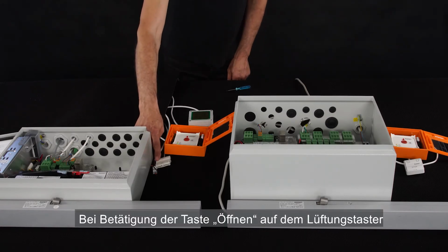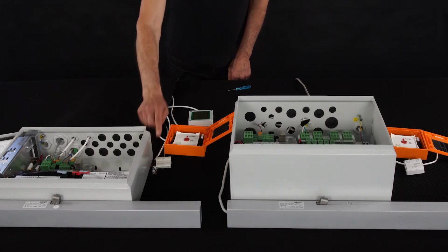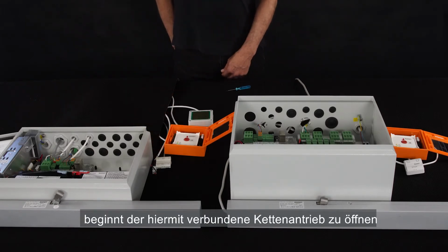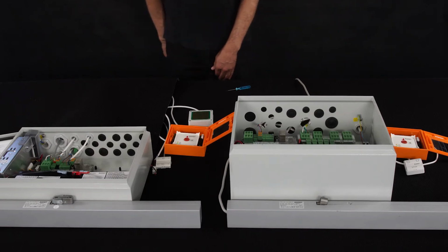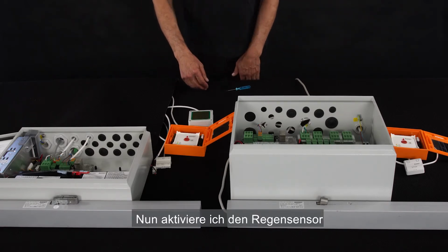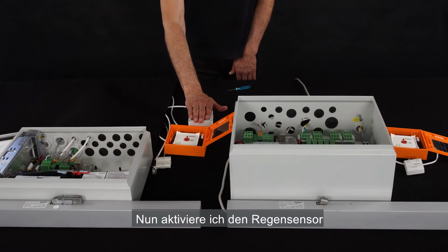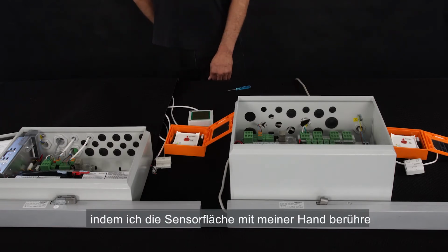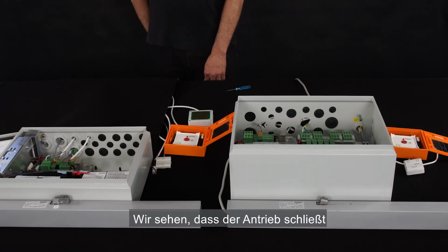If I press open on the manual override switch, the actuator connected to the panel reacts and opens. I now activate the rain sensor by holding my hand over to create humidity, and we see that the actuator is closing.